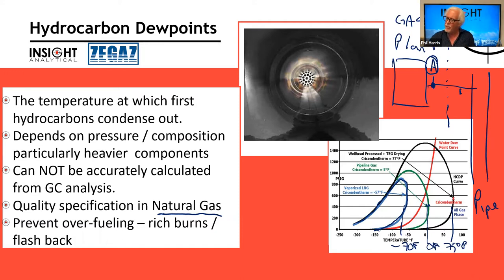If they manually sample, and they find the plant is off spec frequently, then TC may decide they will put their own analyzer over here, or they'll go to a plant and say, you guys got to look at your dew point analyzer and try to figure out whether either your technology doesn't work or it's been poorly implemented.